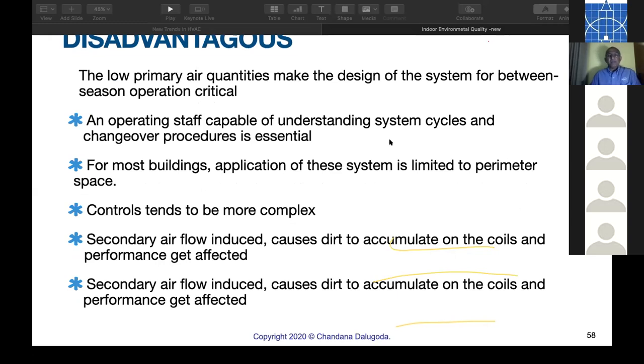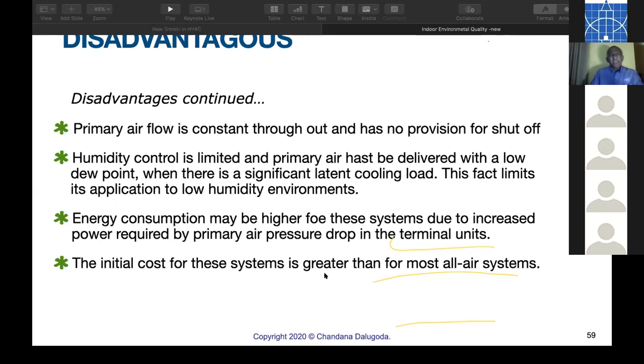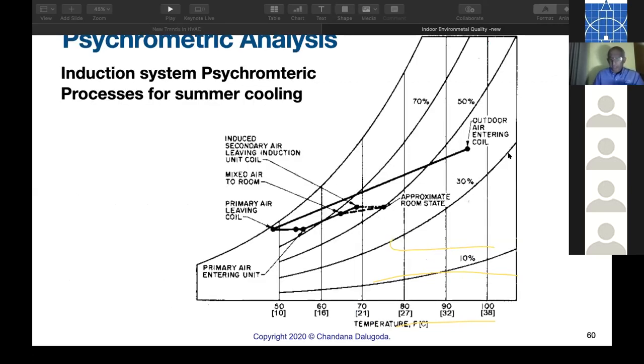Operating staff must be capable of understanding the system cycles and changing procedures. In most building applications, these systems are limited to perimeter spaces only. Controls are a little complex. Secondary airflow induced causes dirt to accumulate on the coils. That is because you can't have an air filter that has a pressure drop on these induced air. Secondary air flow induced causes dirt is the same thing. So these are the disadvantages. And this is how the psychrometric chart looks. This is the central cooling coil. And this is the room cycle. Now, when you look at this, a large dehumidification, remember that later we need this.